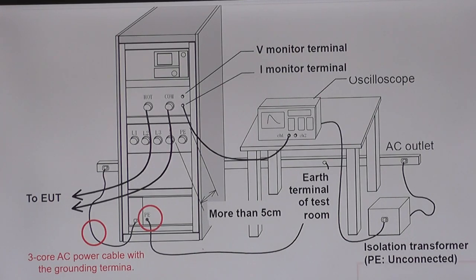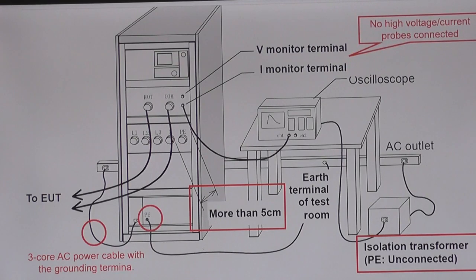Second, use an isolation transformer for the AC power supply of the oscilloscope. In this case, do not connect the oscilloscope's PE terminal. Third, keep the surge output cable and the coaxial monitor cable as far away as possible. Keep them at least 5 centimeters apart. Fourth, due to the risk of electric shock and damage to the measuring devices, do not observe the output waveform directly with a high voltage probe.